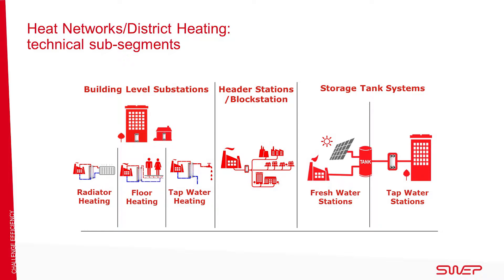District heating has some technical sub-segments. Building level substations can be divided into radiator heating, floor heating and tap water heating. This is the European standard. Header stations or block stations are common in Russia and China. The heat exchanger serves as a pressure breaker between the plant and the substations in residential or industrial buildings.